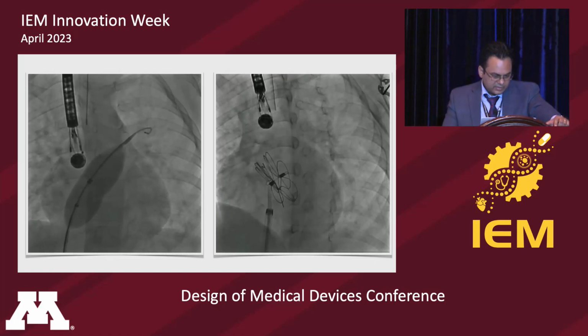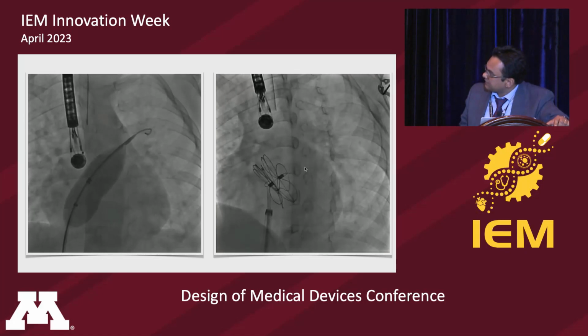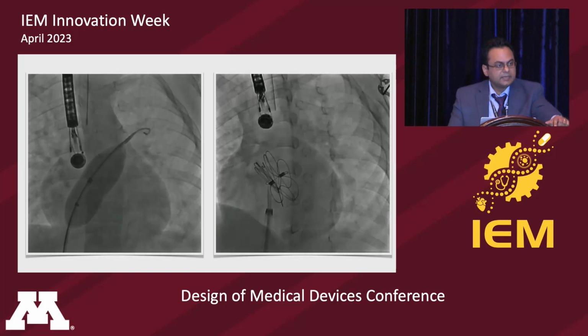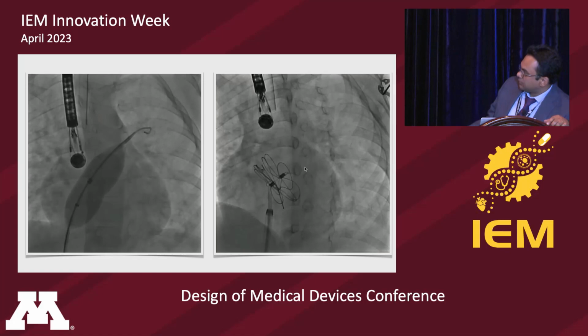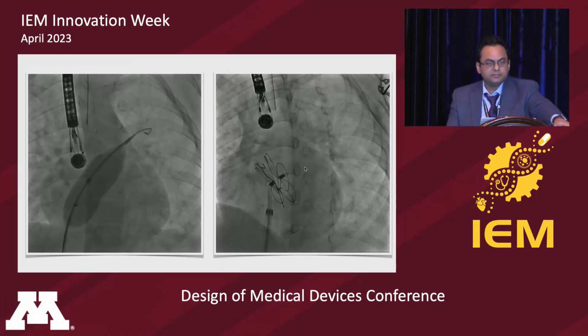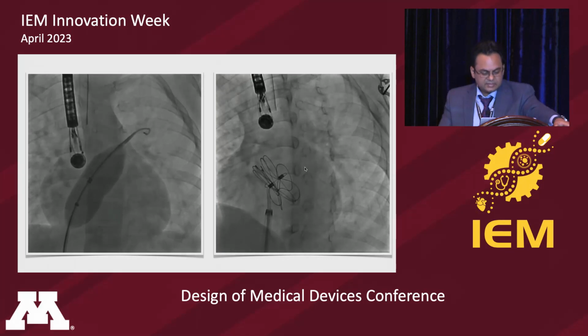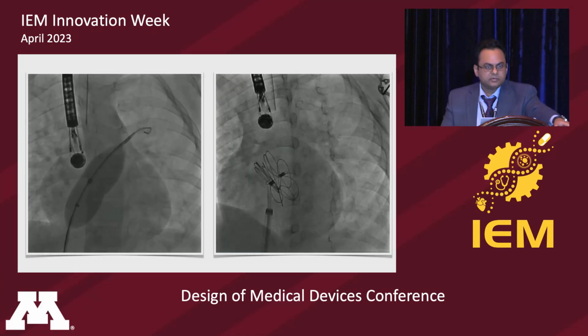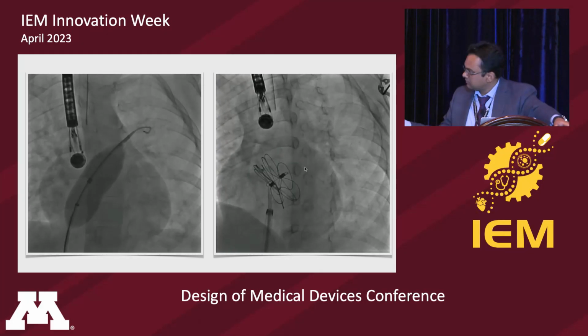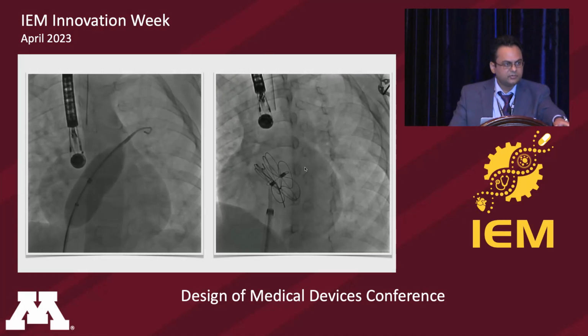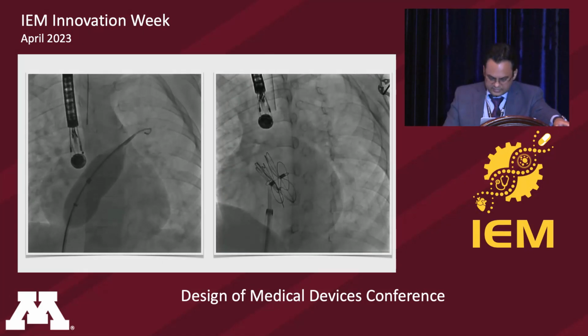And it's a relatively big device for a small child, but you can see this is the left atrial disc, this is the right atrial disc, and the waist in the center, which is capturing. And here the device is locked. You can see this locking loop that's coming out. It's like a metal, U-shaped wire, and it's locked in place, but it's still attached with that wire. So if for some reason you don't like it, you still can retrieve it back into the same delivery catheter that it goes in.